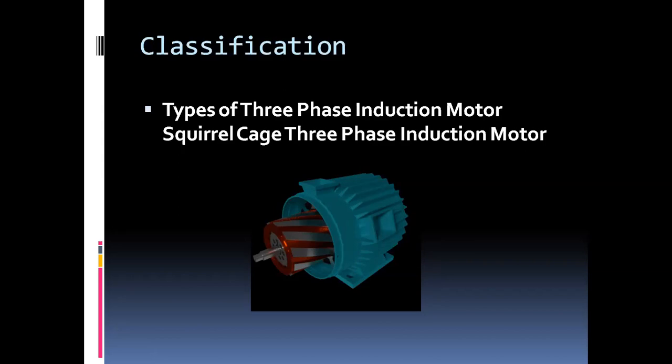It should be noted that the rotor bars are permanently short-circuited on themselves. Hence, it is not possible to add any external resistance in series with the rotor circuit for starting purposes. There are no brushes in this motor, which is one of the reasons for its ruggedness.